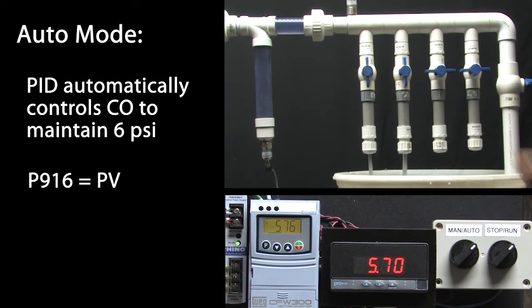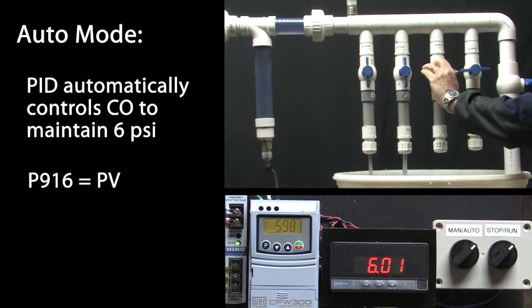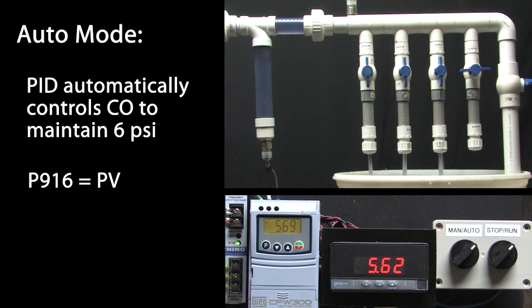How about 2 valves? Wait a few seconds. And yep, it settles out right at 6 psi too. How about 3 valves? Again, give it a few seconds. And sure enough, it settles out right at 6 psi. 4 valves.